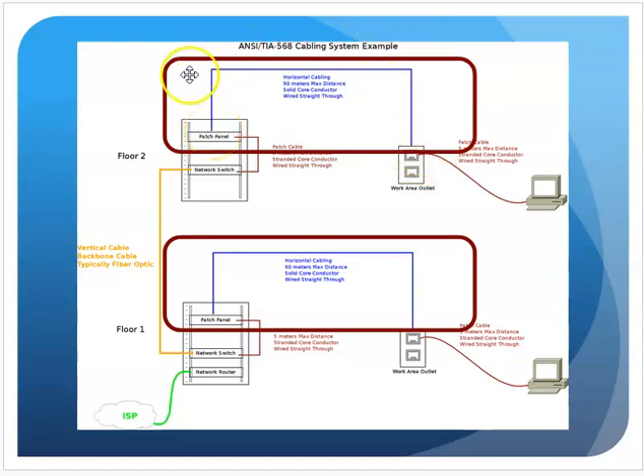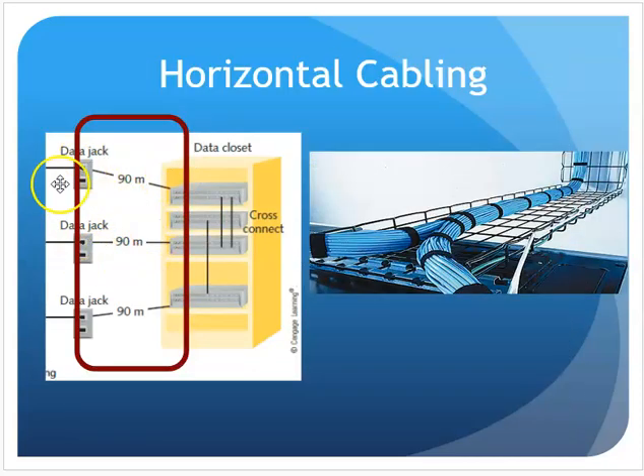And each one of these cable runs coming into a patch panel port gets labeled and identified, so you know it's going to this room or this lab room or this classroom, this port on the wall. That right there, they're saying 90 meters max is what that should be from the outlet into the patch panel. If I look above ceilings, I start seeing this. Cable trays supporting these bundles of cabling going down the hall and into rooms or classrooms or into offices, that sort of thing.